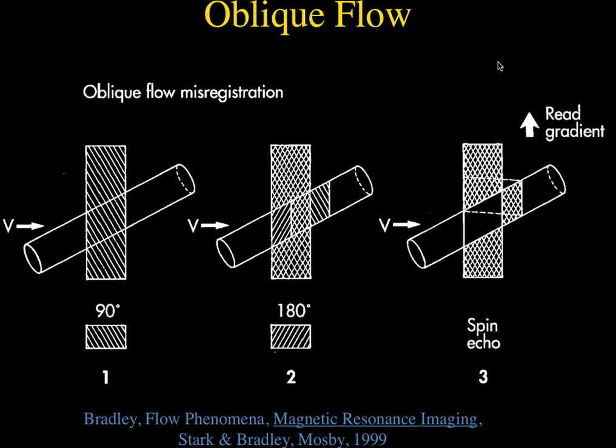When you get the spin echo, and if the read-encoded gradient is up and down, only a small amount of blood in the center sees both the 90- and 180-degree pulses. By the time 2-tau comes around, that blood has displaced itself outside of the actual slice plane. But the computer still thinks it's in the slice plane, and when you do the readout gradient, it will indicate that it has actually moved up.